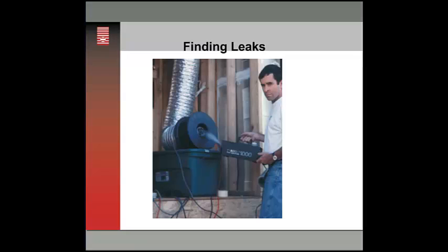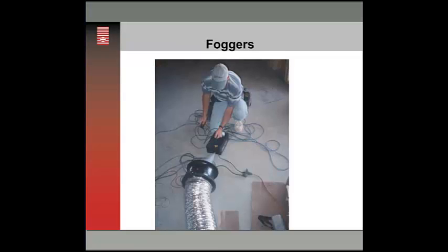And for years, guys have been using theatrical foggers, injecting a fog. It's a little tricky to use. It's not a solve-all. It's an art working with that. You can overwhelm a room with theatrical fog. We'd recommend that the fogger actually goes to the side of the fan. You don't want to bury it down the center of the fan.